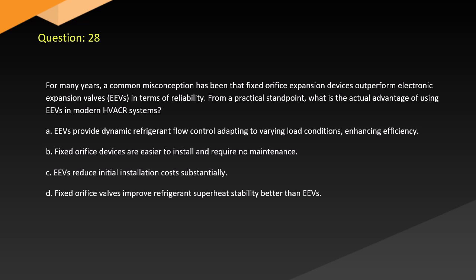Question 28. For many years, a common misconception has been that fixed orifice expansion devices outperform electronic expansion valves (EEVs) in terms of reliability. From a practical standpoint, what is the actual advantage of using EEVs in modern HVACR systems? A. EEVs provide dynamic refrigerant flow control adapting to varying load conditions, enhancing efficiency. B. Fixed orifice devices are easier to install and require no maintenance. C. EEVs reduce initial installation costs substantially. D. Fixed orifice valves improve refrigerant superheat stability better than EEVs.